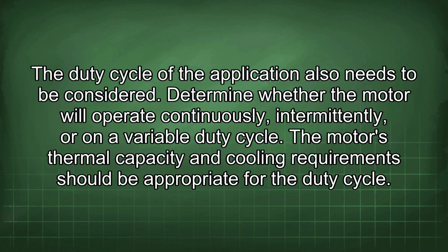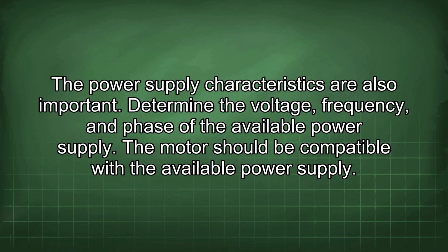The duty cycle of the application also needs to be considered. Determine whether the motor will operate continuously, intermittently, or on a variable duty cycle. The motor's thermal capacity and cooling requirements should be appropriate for the duty cycle. The power supply characteristics are also important. Determine the voltage, frequency, and phase of the available power supply. The motor should be compatible with the available power supply.